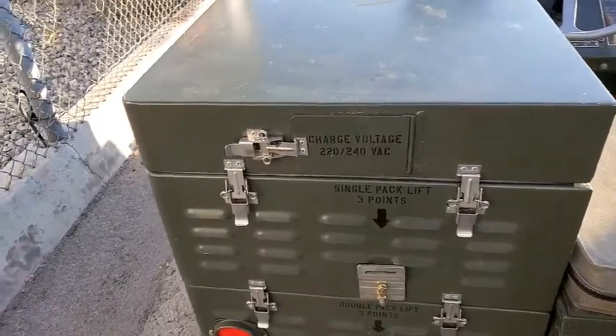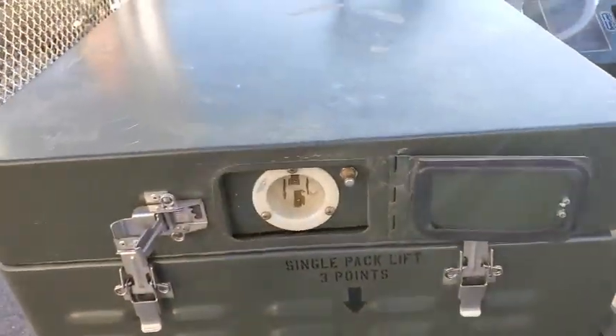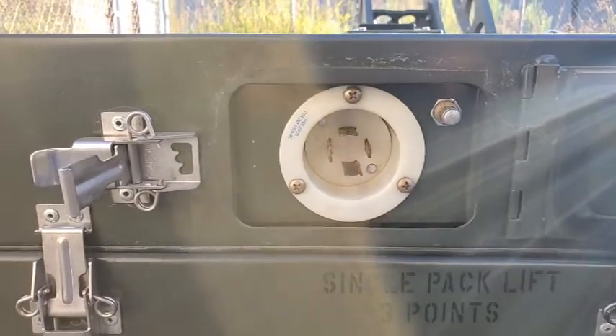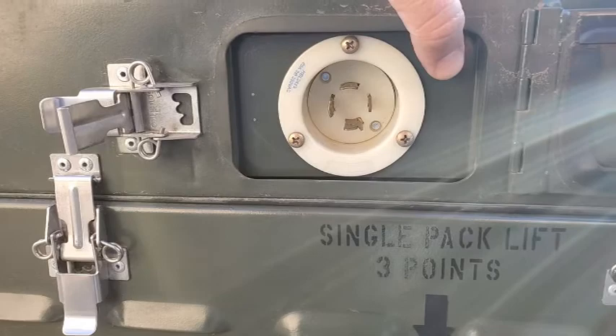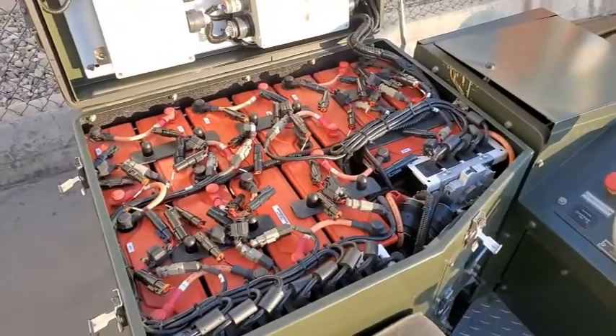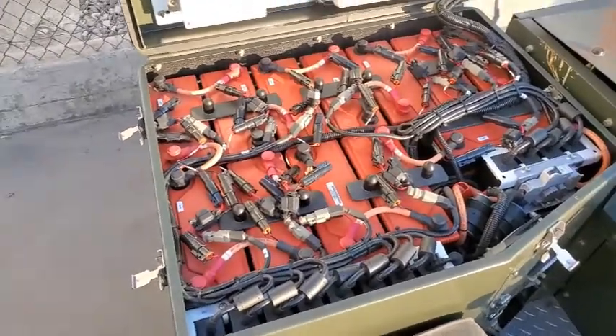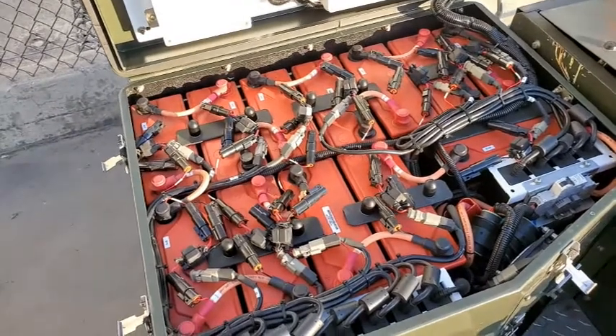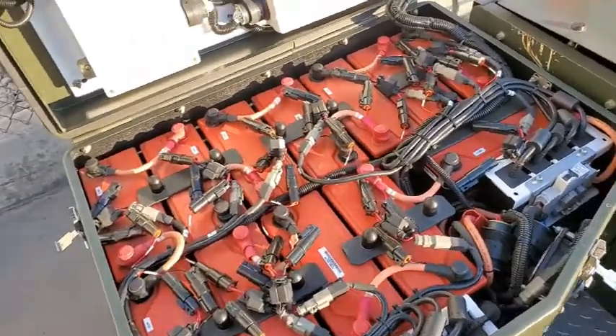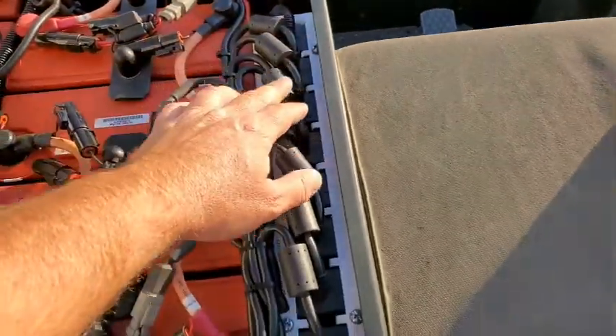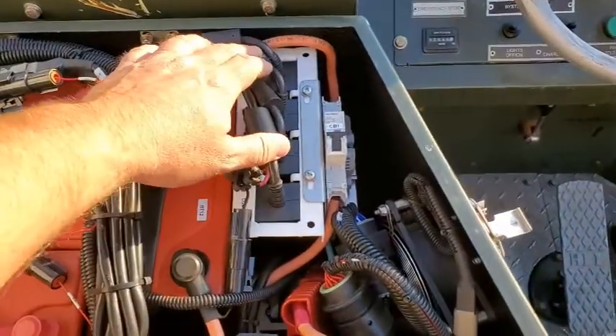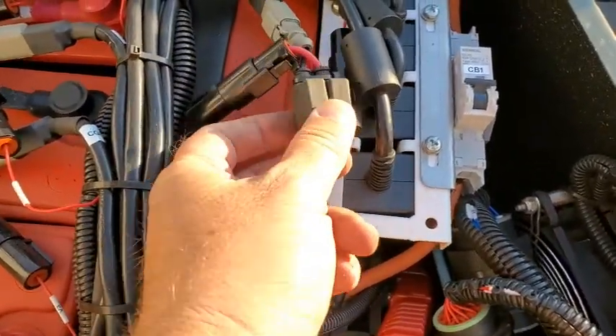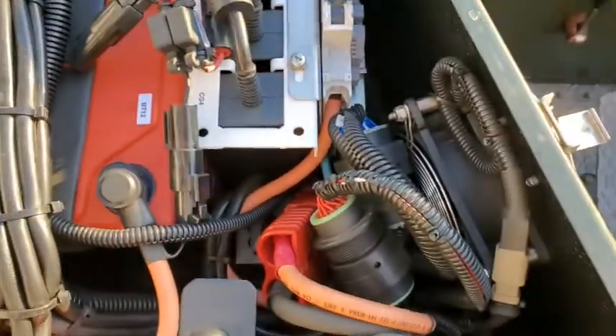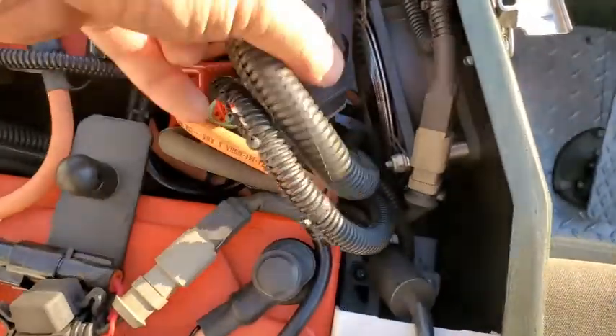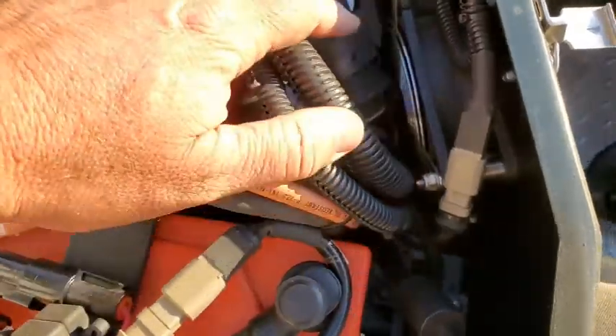Also located on the back of the battery pack is the charging door panel. Pop that open, plug in your charging cable, and start recharging your batteries. Located here is the micro switch that prevents you from starting the unit if this door is open. And on the top of the battery box, you have 12 volt batteries. These are Odyssey PC 1100 models. You have your chargers for each individual battery located up here. Fuses to protect the charging. And then you have 5 cables here that connect the upper half to the lower half. And a cooling fan.